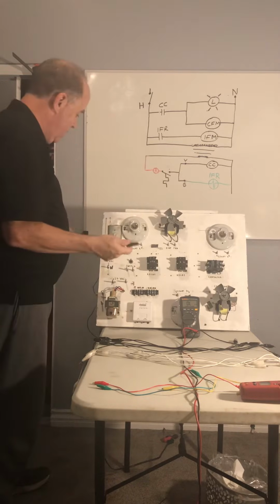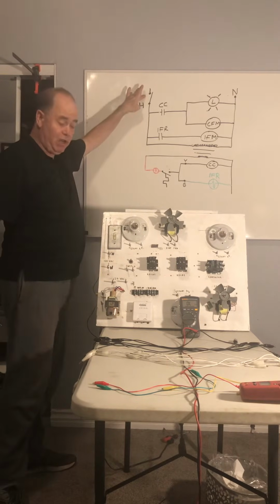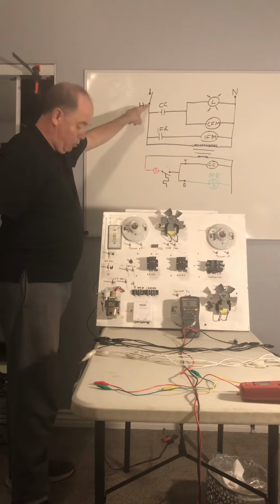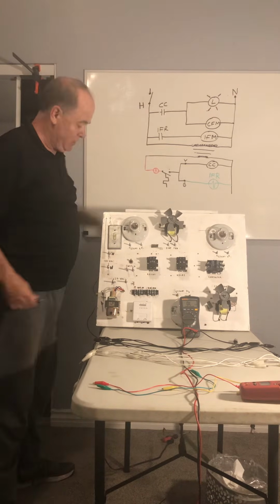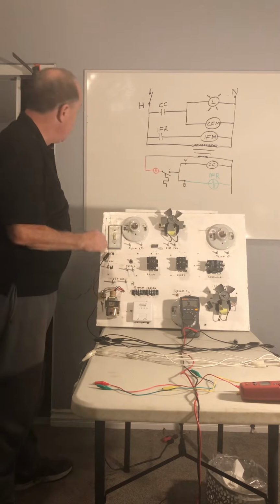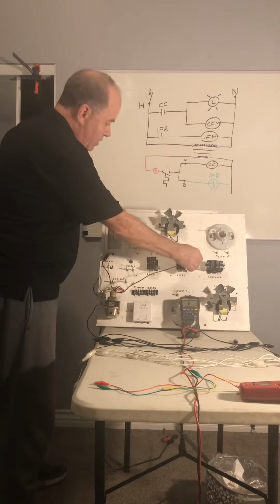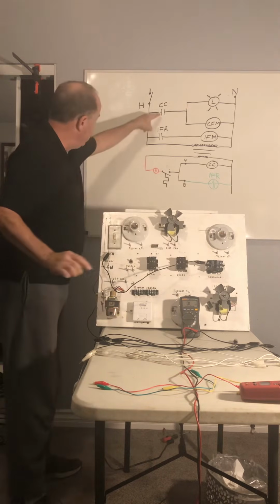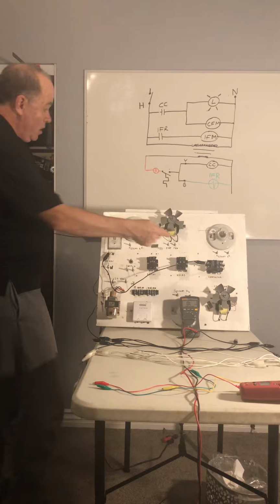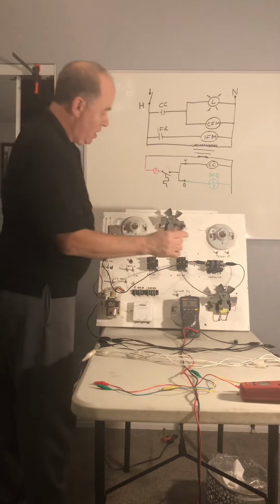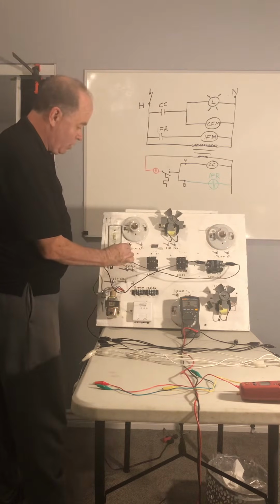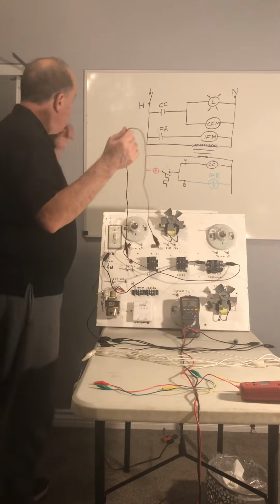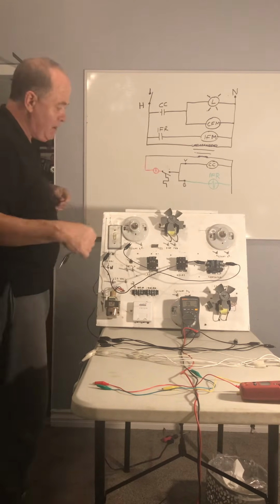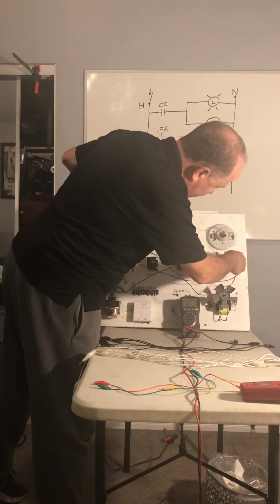So first, the switch is already pre-wired in here. We have hot, and that's at this point right here, and everything's going to come off of hot and go back to neutral over there. So here we have hot going right over to the normally open set of contacts on our contactor, and that would be this wire here. And then we come out of the contact here, and we go to a light, which is going to simulate our compressor. We also come out and go to our condenser fan motor off of this contactor contact, which is down here.